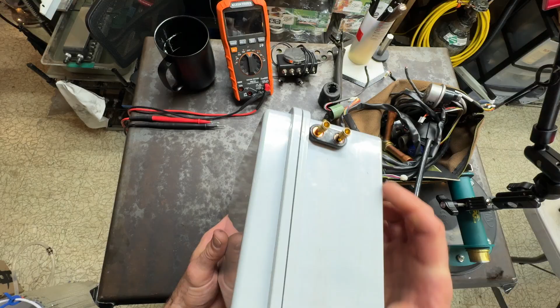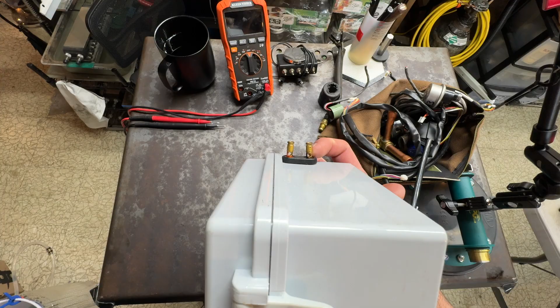This is a 4mm banana jack connection, and that's where your multimeter leads can go, because this is also a power supply. Now it's current regulated, but to use this on, say, a 4 milliamp to 20 milliamp sensor, that's kind of tricky. For those low amperage situations, you really just need another device, and you can get a generic signal generator for $30. But you can still feed voltage into circuits, and that can be a super useful diagnostic tool, but you have to be really careful with what you're doing.